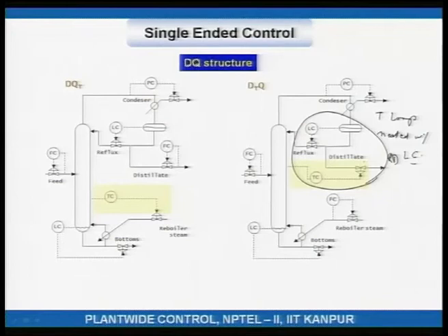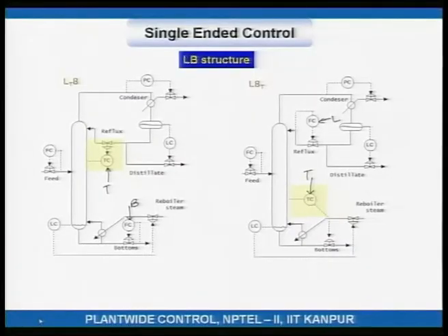right. So, I hope you see, because of the nesting, tight tuning or aggressive tuning of the level controller is justified. Okay. So, this is the exception to the rule where the level controller should not be too aggressive, so that level can absorb disturbances in flow. Okay, this is an exception to that rule.